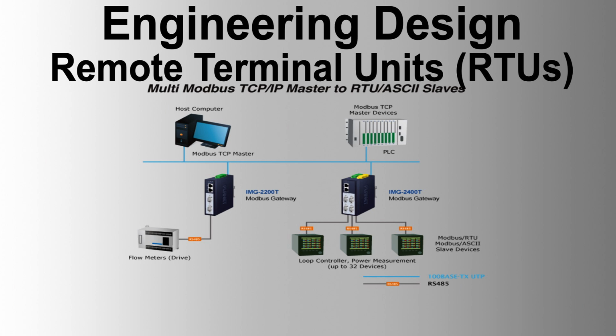Linearization. The RTU should provide linearization of standard thermocouple signals. Signal conversion. 4 to 20 milliampere signals should be converted to 1 to 5 volt DC at the input terminals using a conditioning resistor that maintains an accuracy of at least 0.1%. Range handling. Under-over-range conditions. If the AD operates in under-range or over-range conditions, for samples less than the minimum values specified, the RTU should report 0%. And for samples greater than the maximum values specified, the RTU should report 100%.